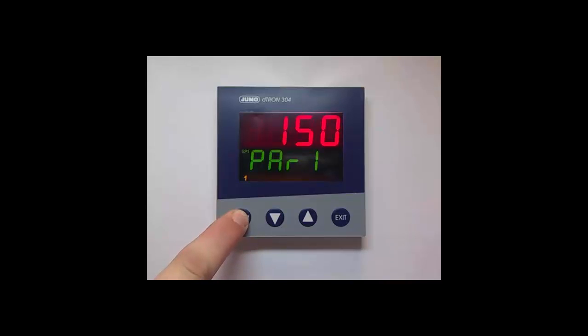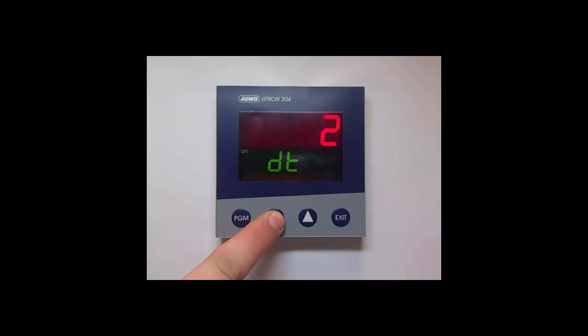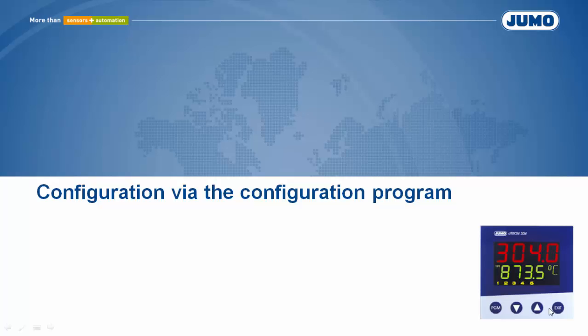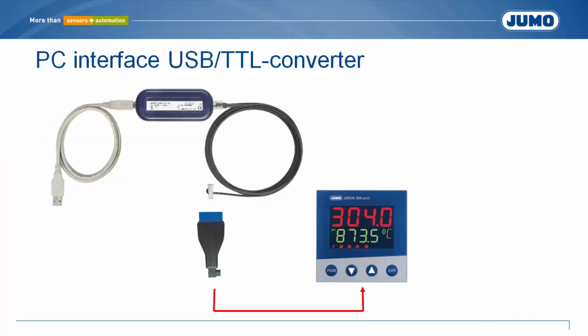The controller has determined the values for the proportional band, the derivative time, the reset time, and furthermore, the cycle time. With the found parameters, the controller controls to the defined set point. The configuration can be done alternatively with a configuration program. For transferring of configuration data, the PC interface USB TTL converter is necessary. The shown PC interface USB TTL converter connects the computer with a d-tron 304.